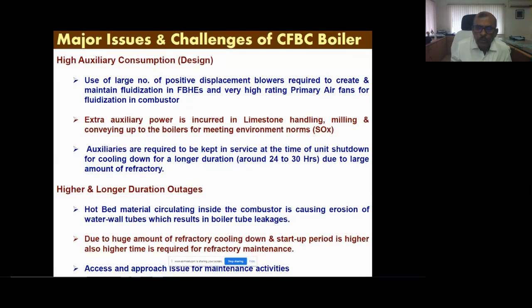So this is now an advantage, because we don't have to do anything for SOx or NOx. We are already complying very well. This is the advantage now. Auxiliary requirement is the major issue. In PF boilers and other boilers, during shutdowns we need to run only minimum auxiliaries, even during startup. But in a CFBC boiler, considering the process and operation requirements, we need to run almost all the auxiliaries during cooling down or startups, which increases the auxiliary consumption.